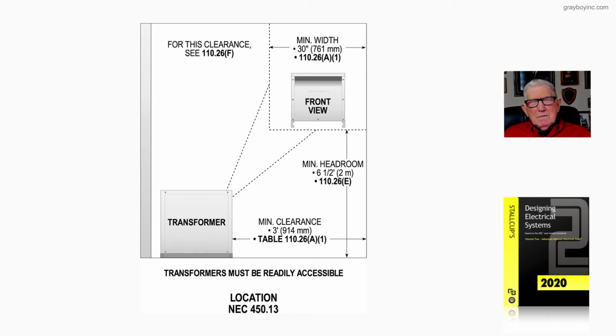And in OSHA 1910.303(g)(1), and Table S-1, you'll find the same rules are required. You need a 30-inch width in front of the equipment, or the width of the transformer, whichever is greater, 3 foot in front of it, and 6.5 foot headroom. Now, these clearances are required so that you can service the transformer for maintenance purposes in accordance with NFPA 70B, and then really just having access around the transformer for working clearances and so forth.